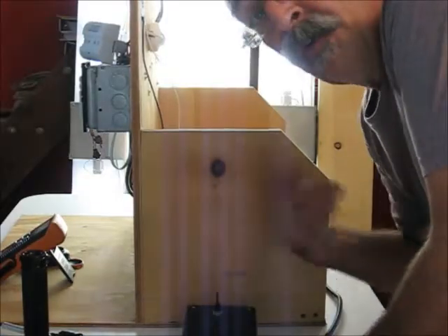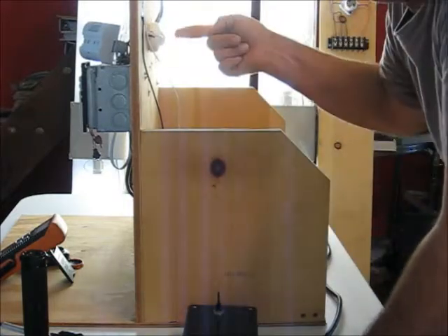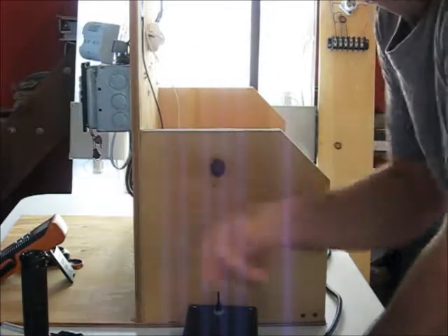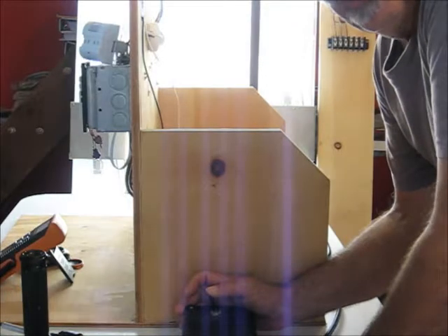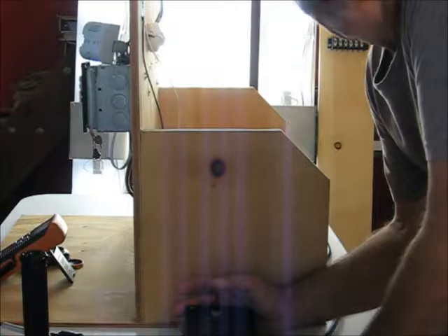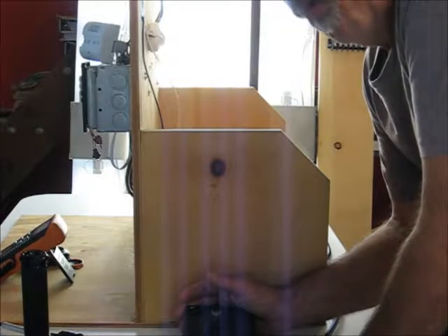Okay, first we have the luxury of running our daylighting up and down, so we do that, and we take the number on the system sensor and the number at our task location and divide, and we get our sensor ratio. And that's apparently going to be pretty good throughout the range because we're under ideal situations. And in this case, I got an average of about 2.44.